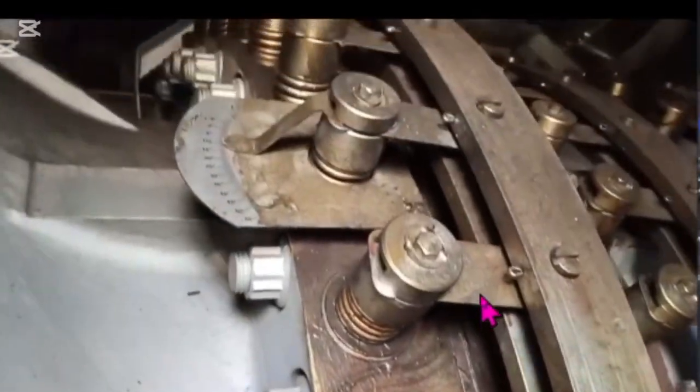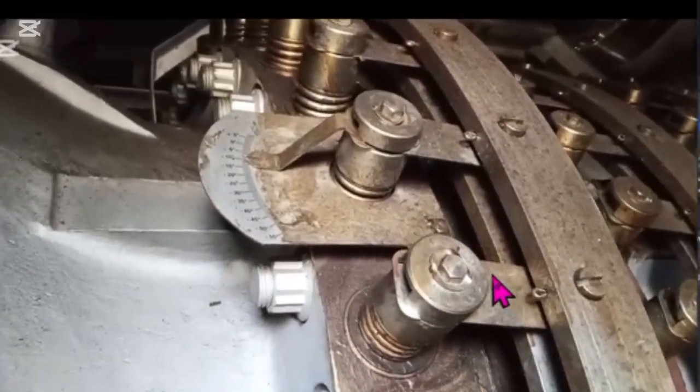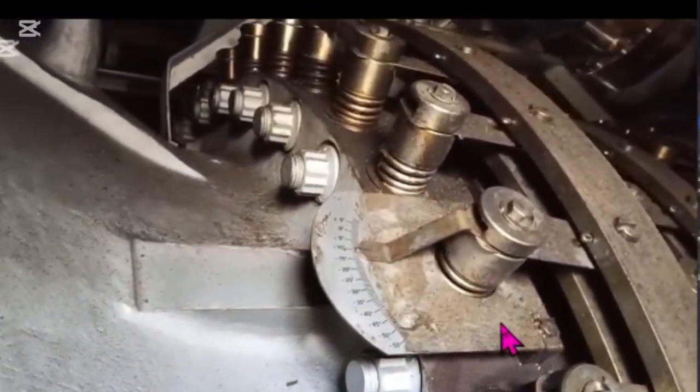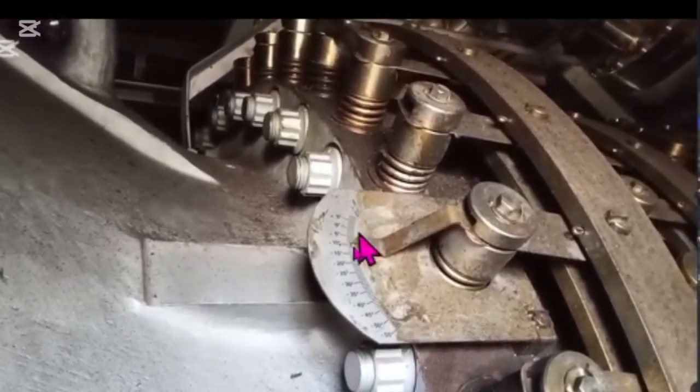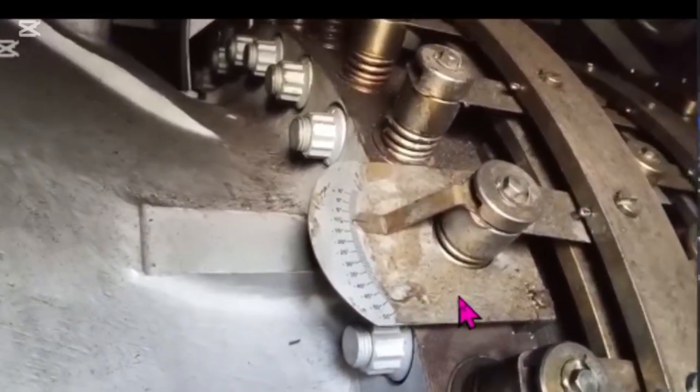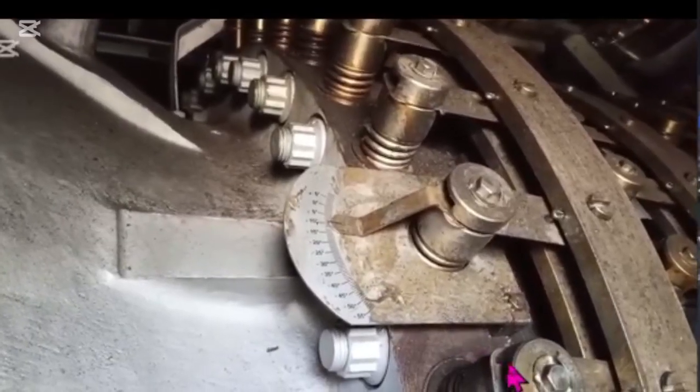On the other hand, when the IGV is fully open, then again we reduce our demand value from 100 to 0, and we followed that. It was also working properly.